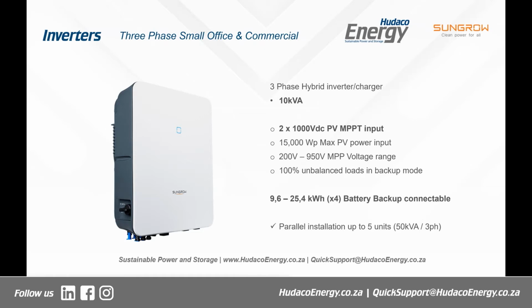So for a client, you may have a 30 kVA demand for a small office building, let's call it a home office. You might want to put, let's call it 50 kilowatt hours, 30 kVA on this to deal both with peaks and through a load shedding time. Very simple. You would do 2 stacks of batteries, 3 inverters side by side. And one of the questions which people often ask is, what happens if I've got unbalanced loads? Do I need to go and redesign the entire distribution board? Do I have to change everything? Do I have to balance it?